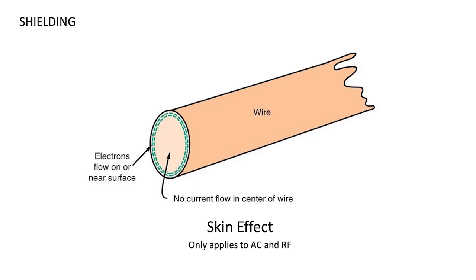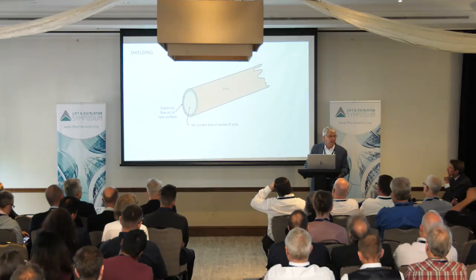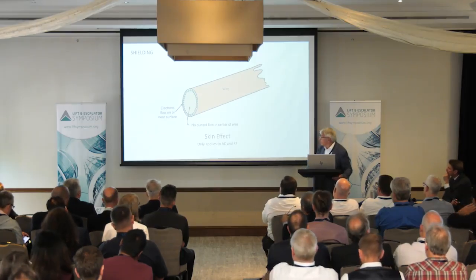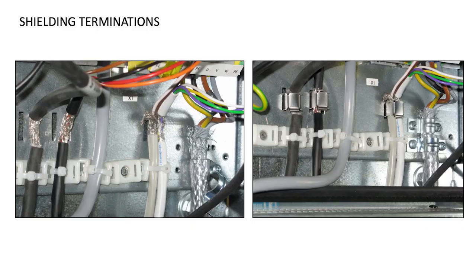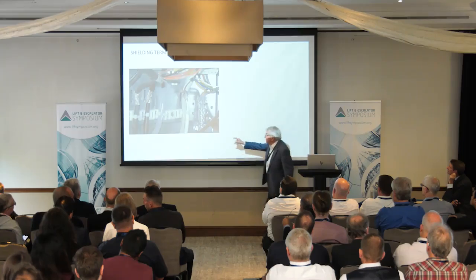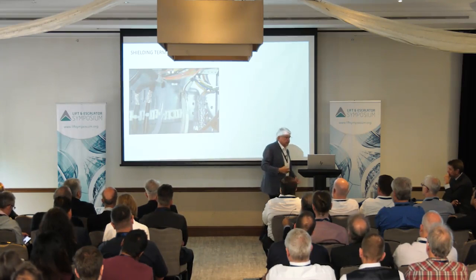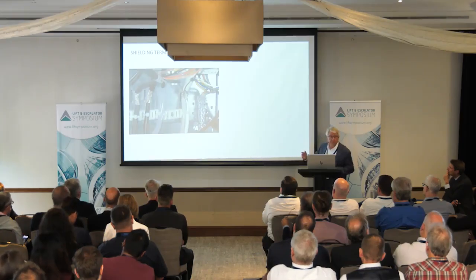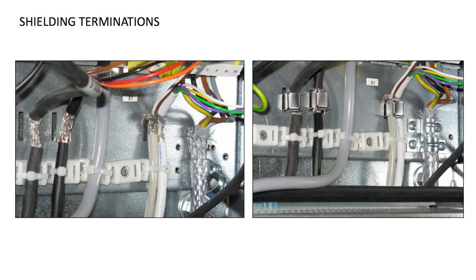But where this comes into effect is how do we terminate our shielding? Here's an example, and you see here these cables have been physically mounted right here. They're mounted, and they're strapped to the insulation. And then you can see that the insulation has been removed from the shielding.